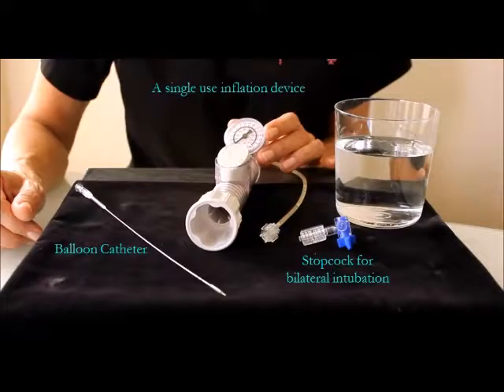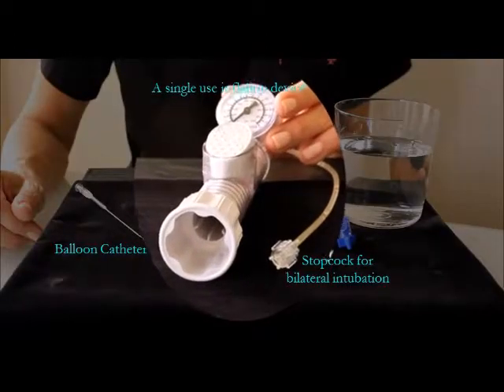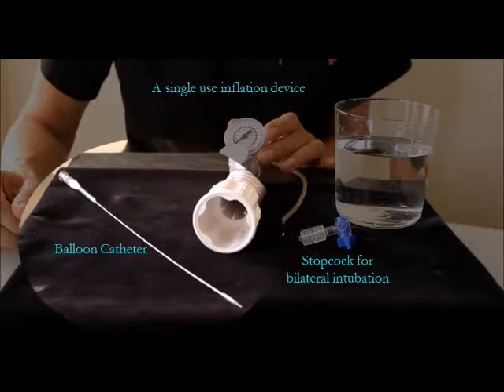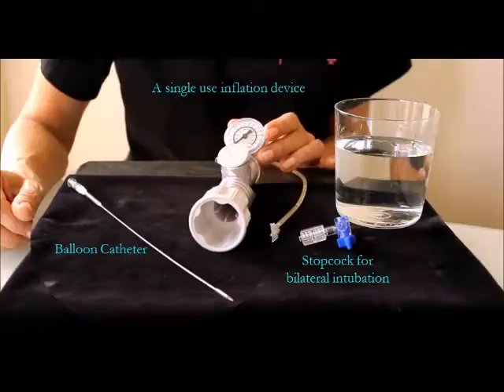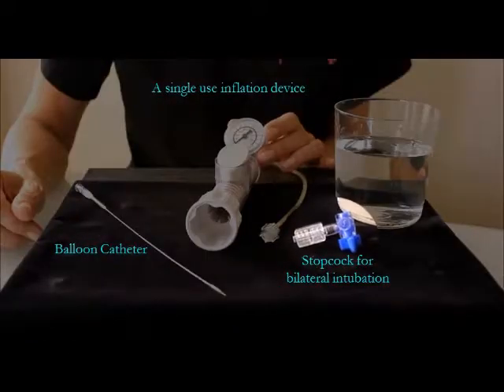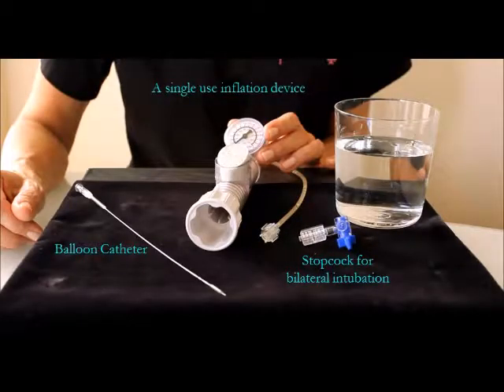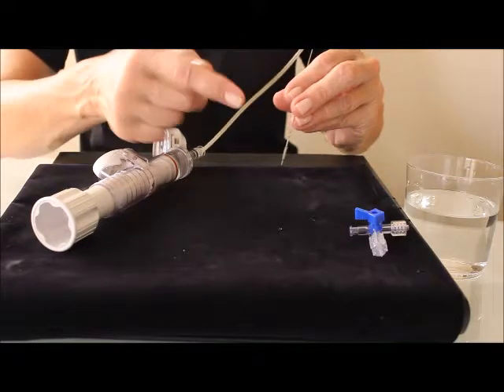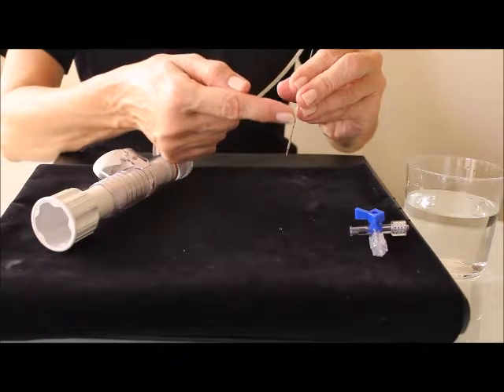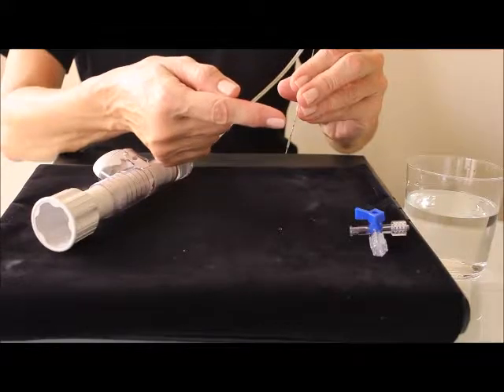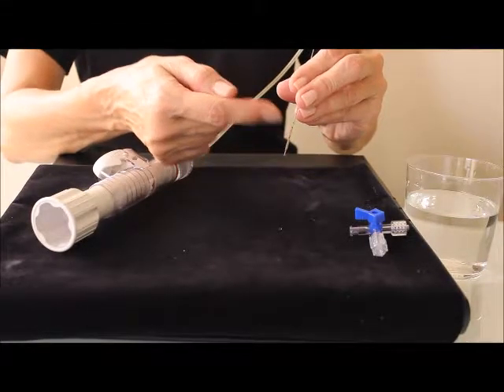Ophtacath is packaged sterile, single-use, in 2 mm or 3 mm kits. Each kit contains a single-use inflation device and balloon catheter. Bilateral kits are also available and contain an inflation device, 2 balloon catheters, and a 4-way stopcock for simultaneous bilateral inflation. The 2 mm catheter is used in patients less than 30 months of age. The 3 mm balloon is for patients 30 months and older. The term 2 mm and 3 mm refers to the outer diameter of the inflated balloon.